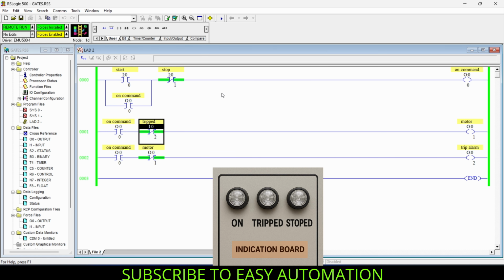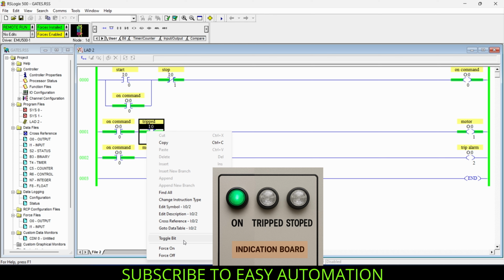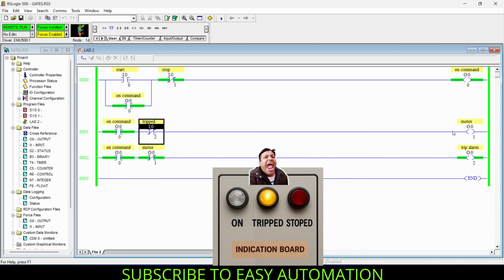So now our program is in idle condition. That means our NO contacts are NO and NC contacts are NC and no output coil is energized here. So if I press our start push button and release it, then our on command will get started, and by using that on command our motor will start. And if our motor gets tripped, then this trip feedback will get high and our motor will get off and the trip alarm will go high.